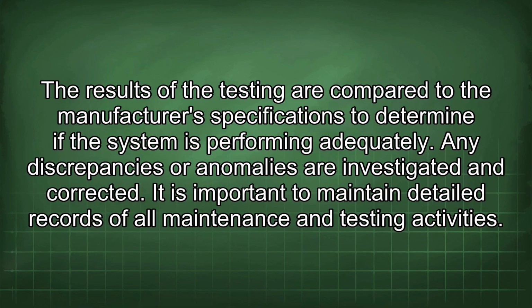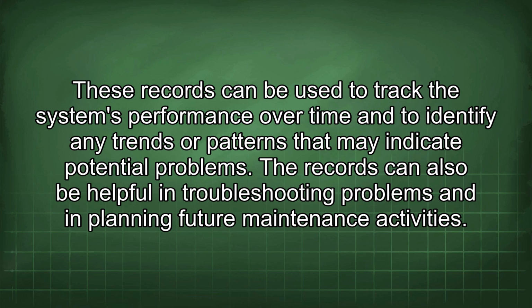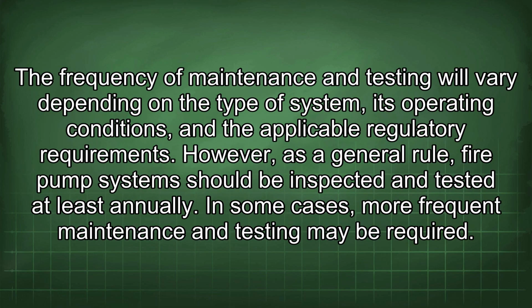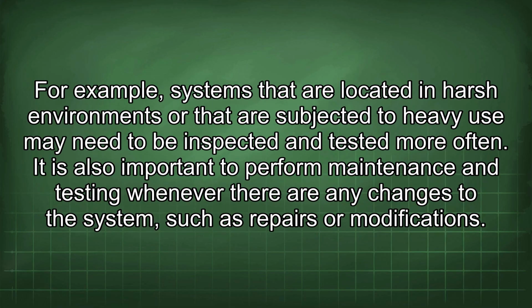It is important to maintain detailed records of all maintenance and testing activities. These records can be used to track the system's performance over time and to identify any trends or patterns that may indicate potential problems. The records can also be helpful in troubleshooting problems and in planning future maintenance activities. The frequency of maintenance and testing will vary depending on the type of system, its operating conditions, and the applicable regulatory requirements. However, as a general rule, fire pump systems should be inspected and tested at least annually. In some cases, more frequent maintenance and testing may be required. For example, systems that are located in harsh environments or that are subjected to heavy use may need to be inspected and tested more often.